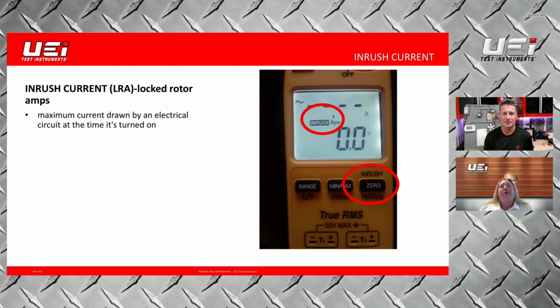Which stands for your locked rotor amps. And that's important because your meter may have a min-max function, but the inrush current happens so quickly that most of the time your max button won't capture it. So it's that initial startup. We've built in your locked rotor amps or inrush current so you can see how much energy is drawn upon the initial startup.